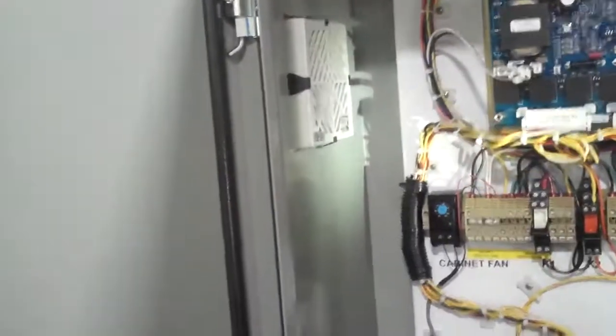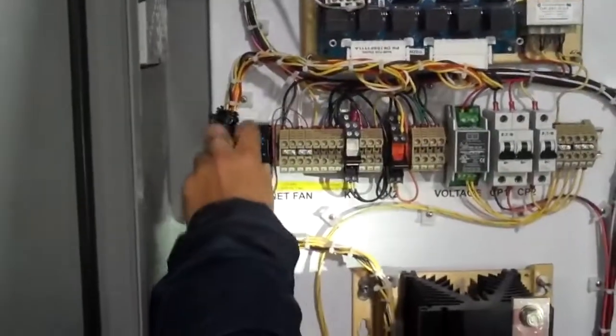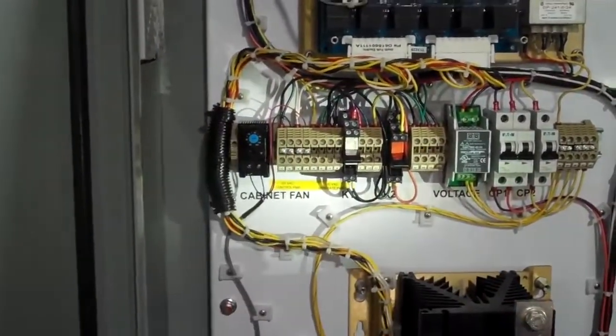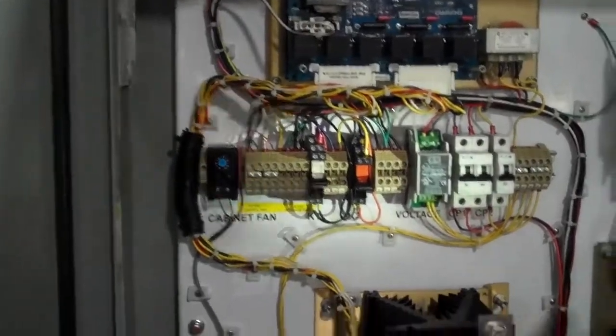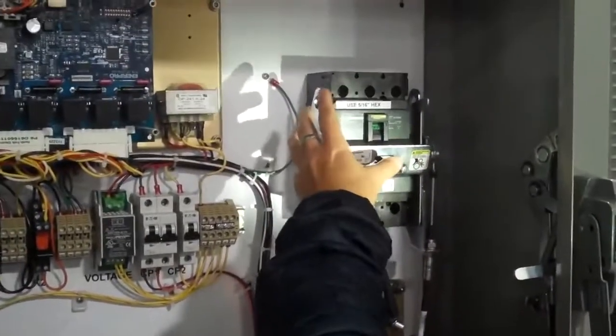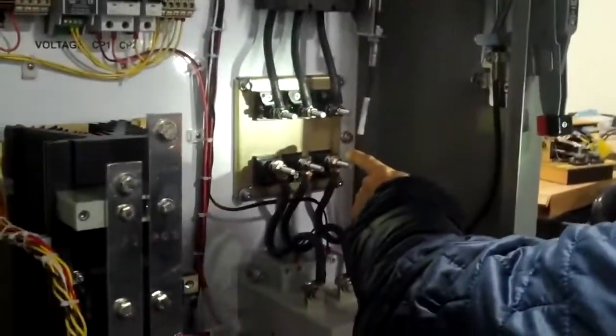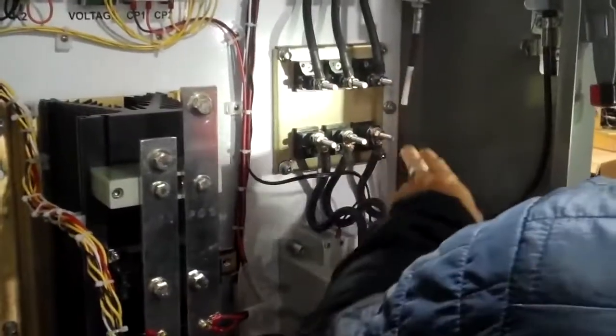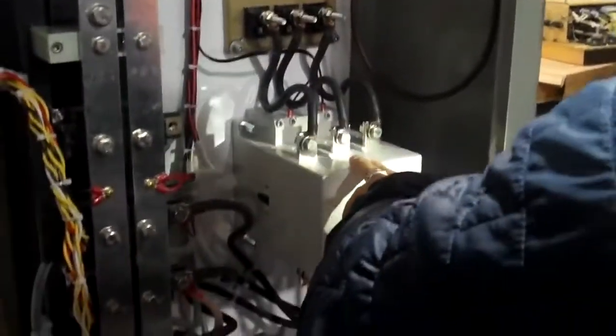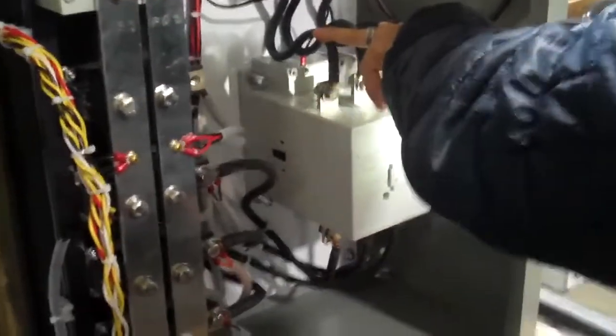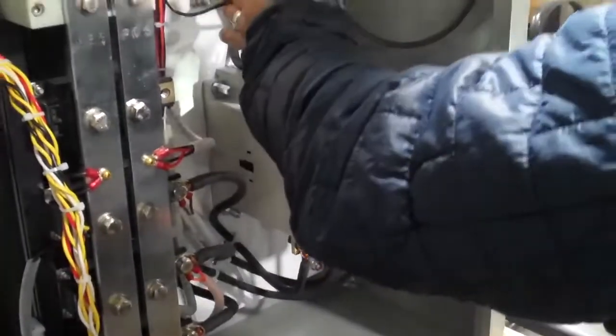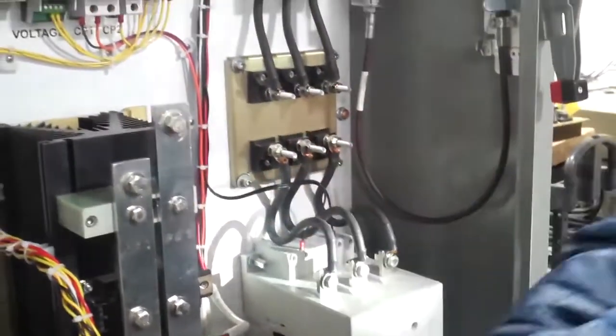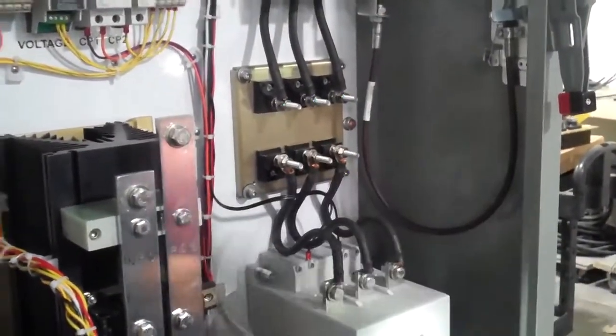We have here the cabinet fan, and it has its exhaust. It also has a cabinet fan thermostat that will be set by the customer. We have the 200 amp circuit breaker with its flange disconnect feeding 3 fuses. Then from the fuse terminal plug, it goes into a DC AC contactor, 3 AC coming in, 3 AC coming out, and we have 120 volts AC to energize that contactor.